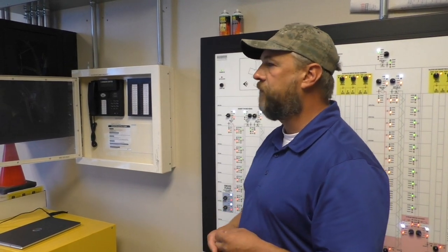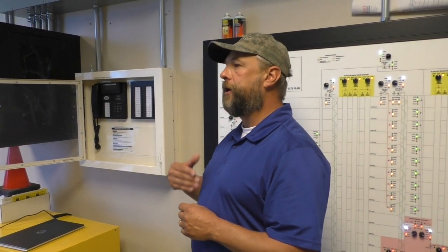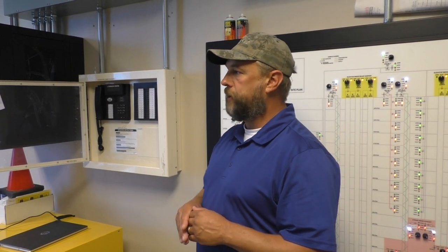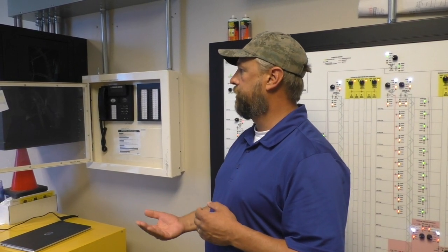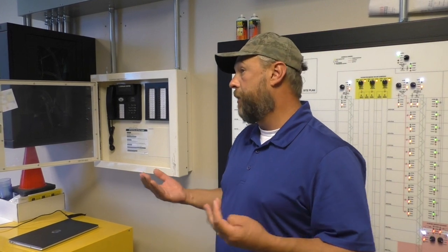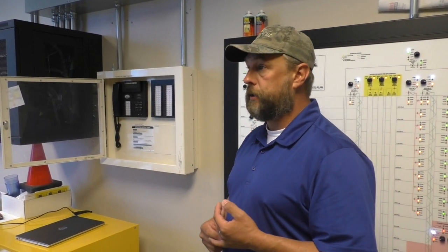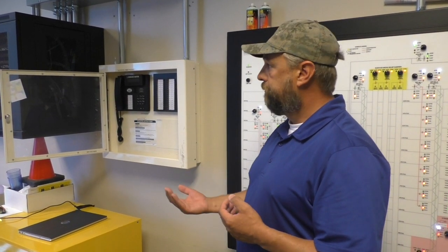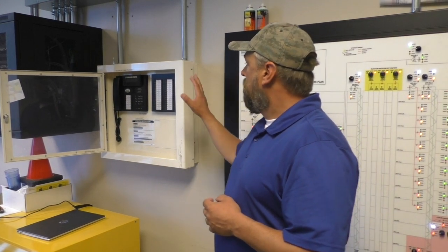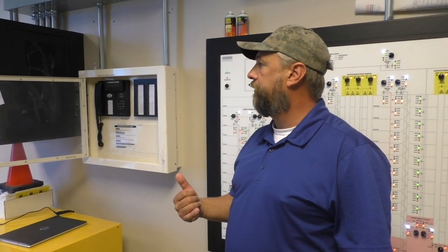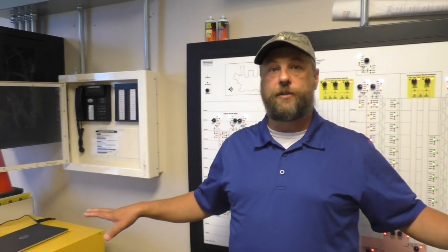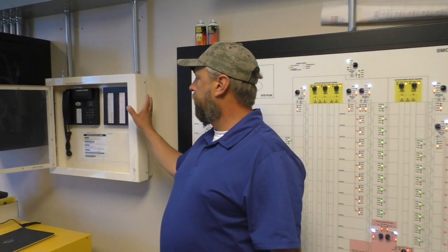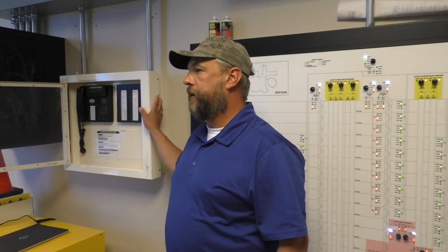If somebody on the 15th floor pushes a button and they don't answer, monitoring errs on the side of caution and dispatches you to come out anyway, because they don't know if somebody is truly in distress. This will not communicate any history to the fire alarm panel. So if you show up and you had an alarm on the 15th floor, but the fire alarm system does not have any history of that, try and refer back to the Area of Refuge.